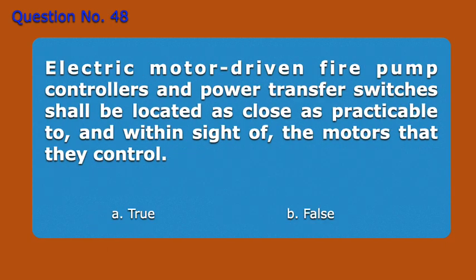Question number 48. Electric motor-driven fire pump controllers and power transfer switches shall be located as close as practicable to, and within sight of, the motors that they control. A. True. B. False. Answer A. True.